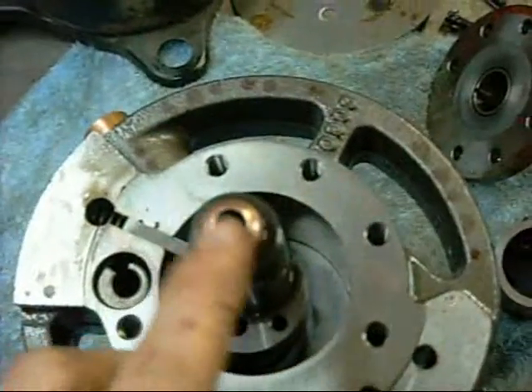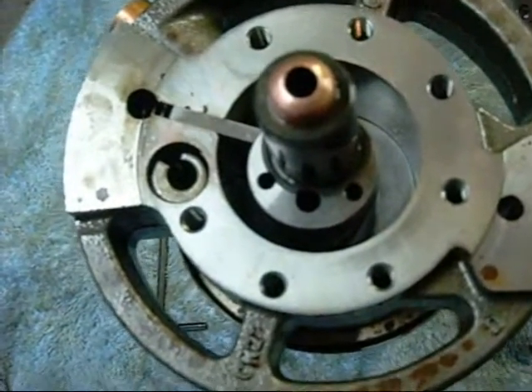This here is also your oil pump. It just uses centrifugal force to siphon oil up through the spindle and spray it out through these galleries into the rotor housing as well as the main motor bearing down here. They don't actually have a separate oil pump or anything — it's just centrifugal force.